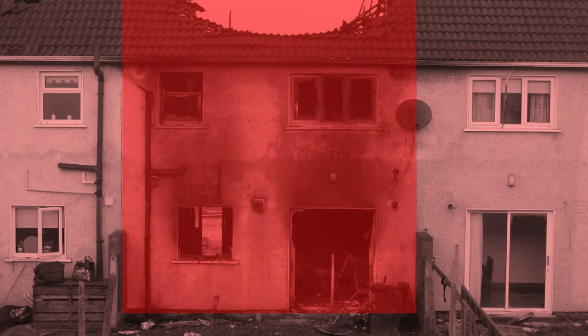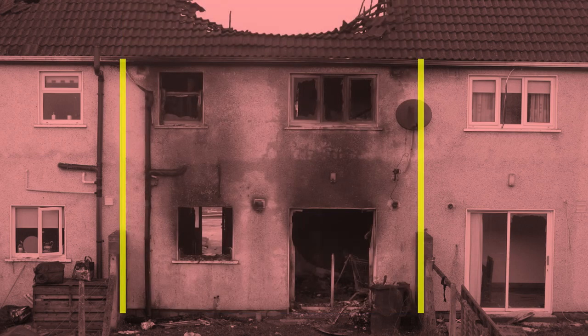Going back to the picture, we can see the house in the middle of the terrace has suffered a significant fire, but the buildings on either side are largely intact — there are still windows and they still look like they're in occupation. That's probably because within the masonry wall, there is some sort of cavity barrier installed on the line of those walls. That stopped the fire from spreading within the cavity to the neighbouring property.